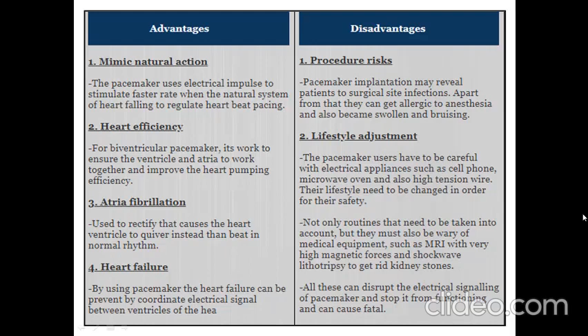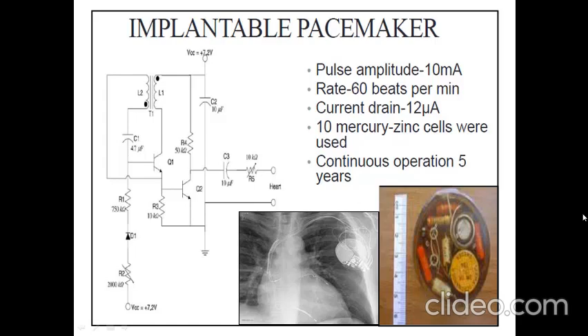So you just see the diagram of an implantable pacemaker. Early on it used to be around 5 cm in size, but now it is on the millimeter scale. An early transistor type implantable pacemaker is shown here, using a pulse amplitude of 10 milliamps, a rate of 60 beats per minute and a current of 12 microamps, and 10 mercury zinc cells were used as the power source. And you notice that continuous operation of 5 years was expected for this type of implantable pacemaker.